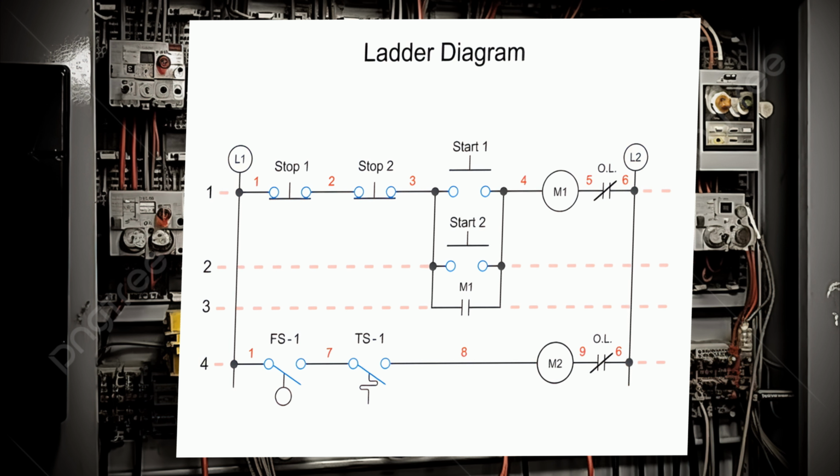Rung reference numbers are usually in parentheses adjacent to the rung in which auxiliary coil contacts and contactors are used. In this schematic, the motor coil on rung 1, M1, is referencing a normally open contact, M1. Thus, a 3 in parentheses is placed here. This reference number doesn't have a line over it because the M1 contact in this circuit is normally open. However, if the contact was normally closed, it would have a line over the rung reference number.